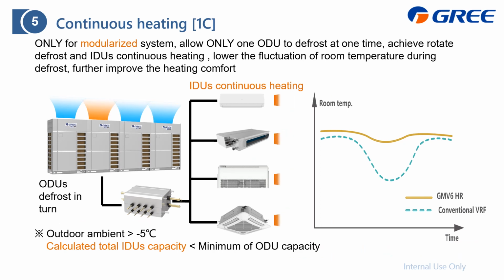Continuously heating function code 1C. This is a special function for modularized heat recovery system. That means during the defrost for this modularized heat recovery system, if this condition is satisfied, then the outdoor unit will take turns to do the defrost. And the benefit is the indoor unit will not stop. We can continuously offer the heating.